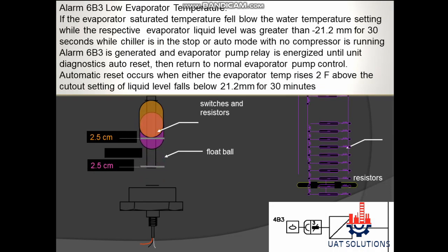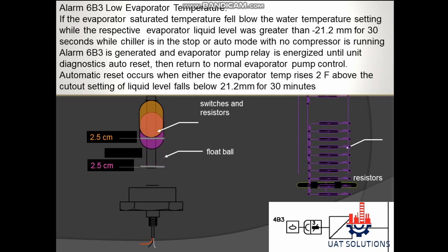Alarm 6B3 — Low Evaporator Temperature: If the evaporator saturated temperature falls below the water temperature setting while the respective evaporator liquid level was greater than minus 21.2 millimeters for 30 seconds, while the chiller is in stop or auto mode with no compressor running, alarm 6B3 is generated and the evaporator pump relay is energized until unit diagnostics auto reset, then returns to normal evaporator pump control.